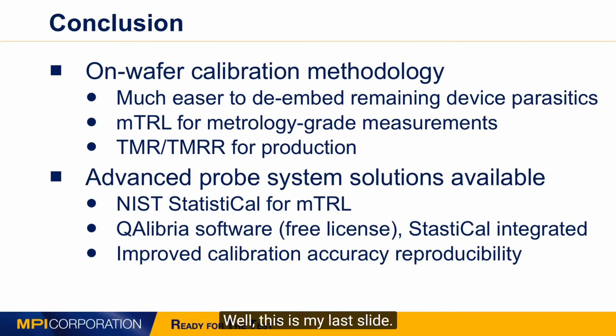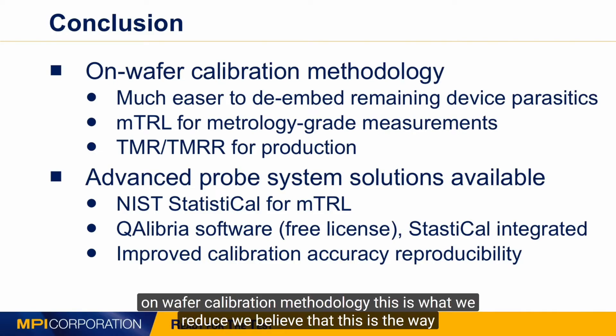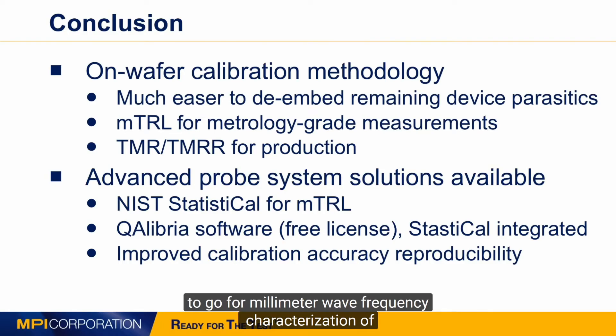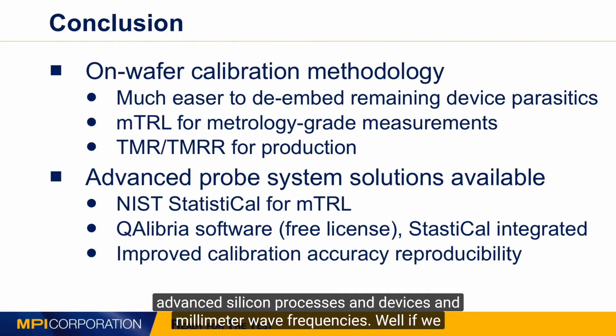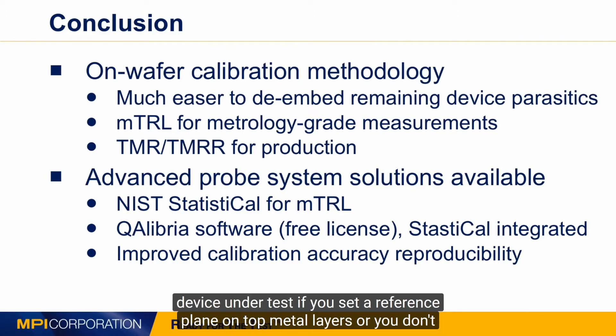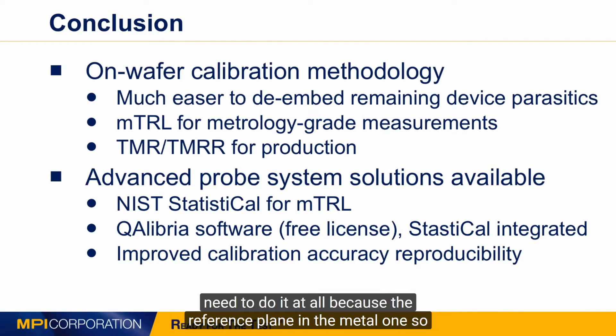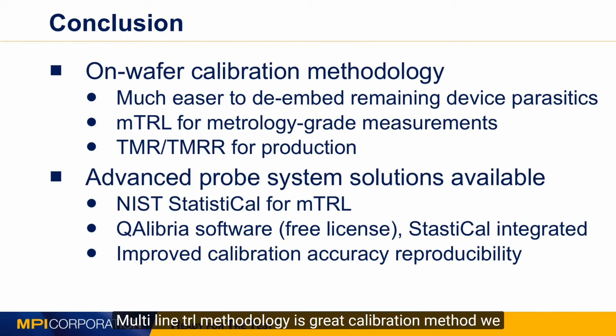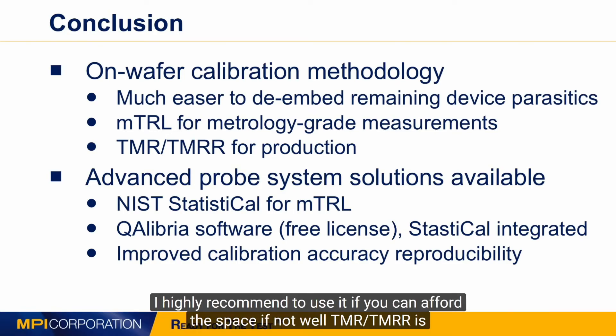That's my last slide. To conclude, on the topic of calibration methodology, we believe multi-line TRL is the way to go for millimeter-wave characterization of advanced silicon processes and devices. It makes it much easier to de-embed the remaining parasitics of the device under test — whether you set a reference plane on the top metal layers or on metal one. Multi-line TRL is a metrology-grade calibration method and we highly recommend using it if you can afford the space.